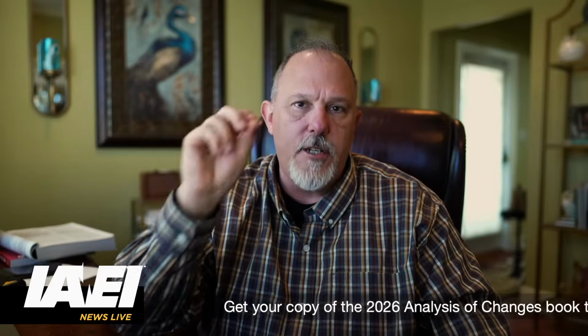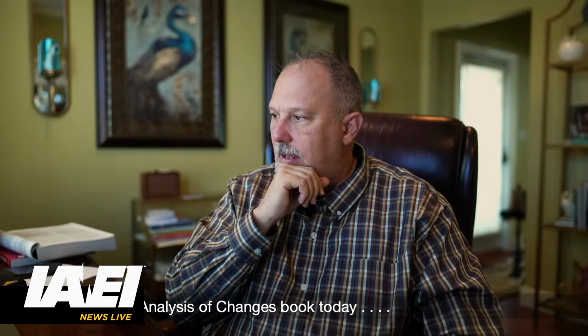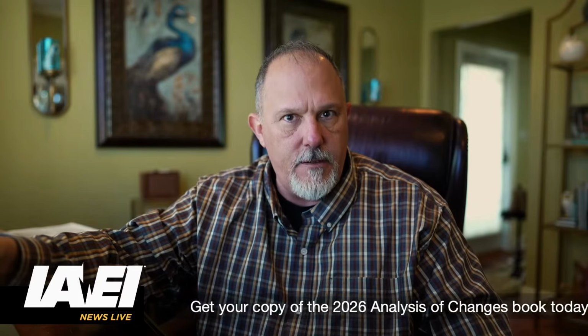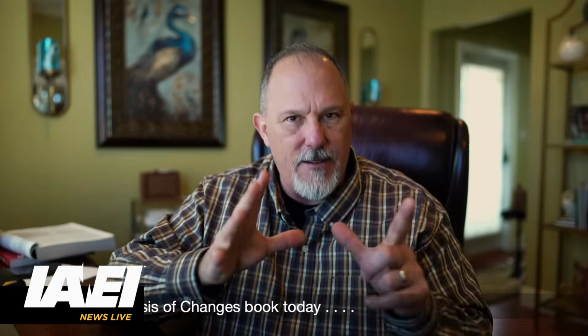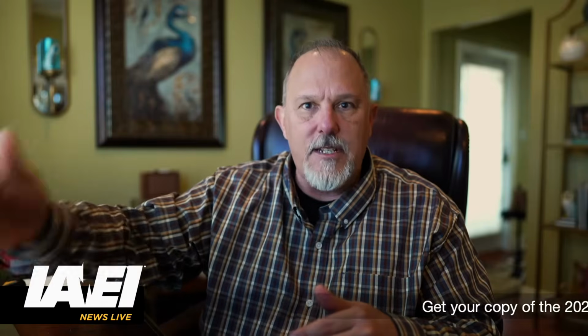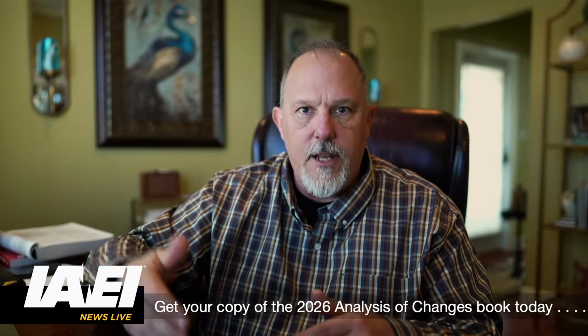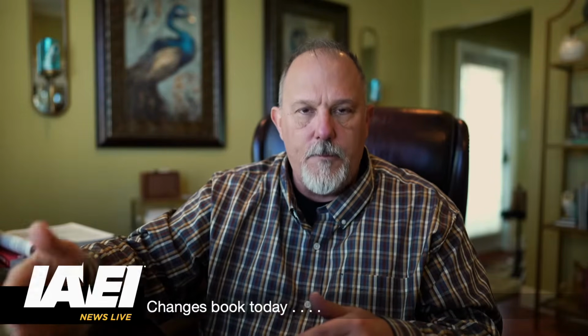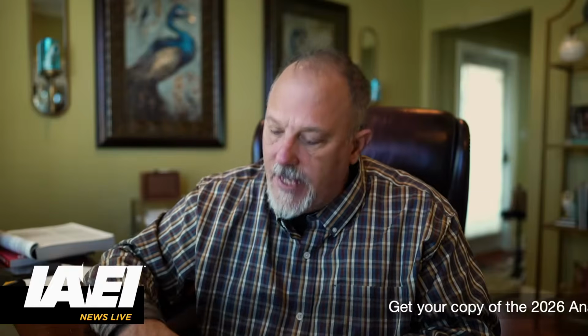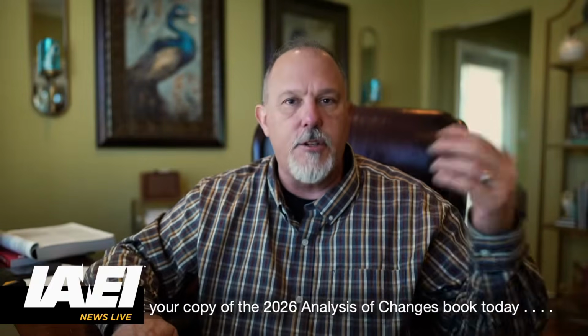The bottom line is that I think OSHA would say they settled the debate, sort of, because the act of establishing an electrically safe work condition is energized work. Think about that. Think about what I just said. The act of establishing an electrically safe work condition is energized work. When you turn something off, what do you do? What's the process? Go to 70E. 70E will tell you, establishing an electrically safe work condition, you turn something off, you release all the stored energy, you lock and tag things out, but then you need to measure and verify absence of voltage.